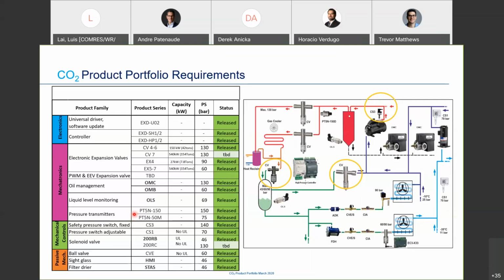Some pressure transducers. These are the Alco German pressure transducers, but Retail Solutions also has, I'll show you, pressure transducers rated to 2,000 pounds that are currently being used on systems in North America. A high pressure safety switch. Europe has developed an adjustable low pressure safety switch, which is not UL approved yet. So I've indicated that we cannot sell that yet in North America, or a higher pressure solenoid valve, which is not yet UL approved. So there's a few products in there that are not yet UL approved, but many still are.